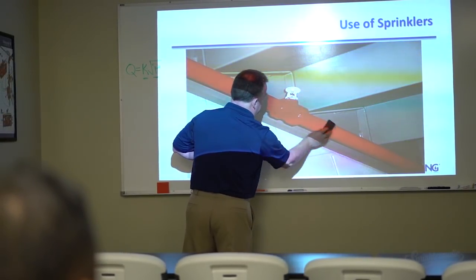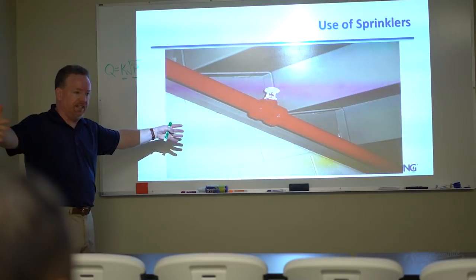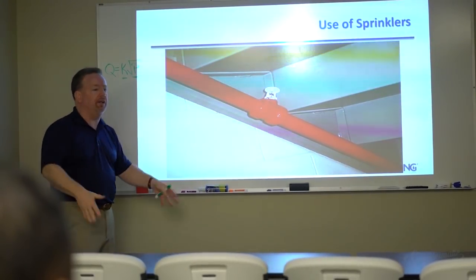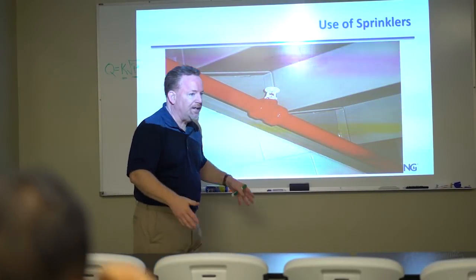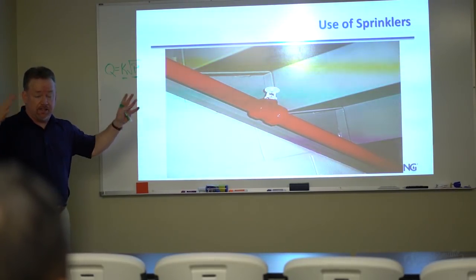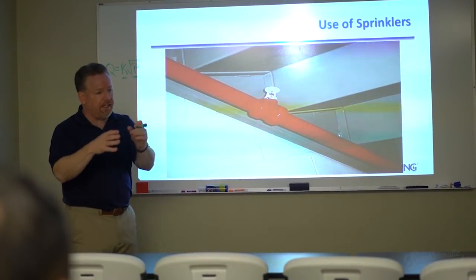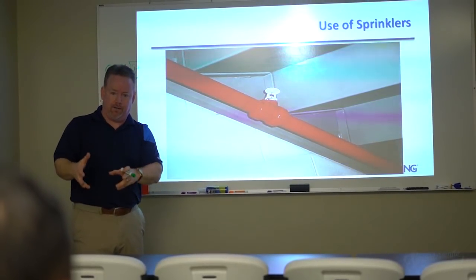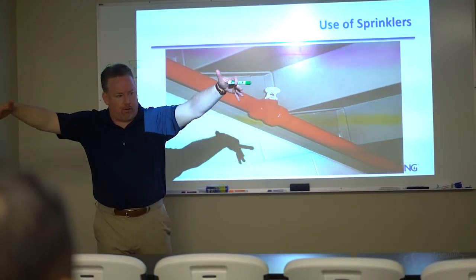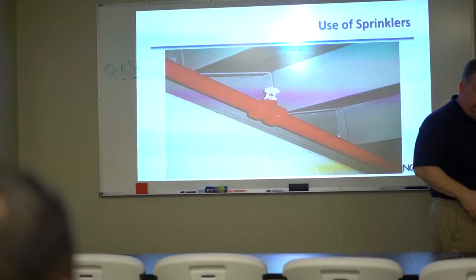Underneath each sprinkler is a certain area of floor it's responsible to cover — maybe 130 square feet, maybe 225 square feet, or even up to 400 square feet, like a 20 by 20 area. The sprinkler is required to cover that area with a specific density of water.